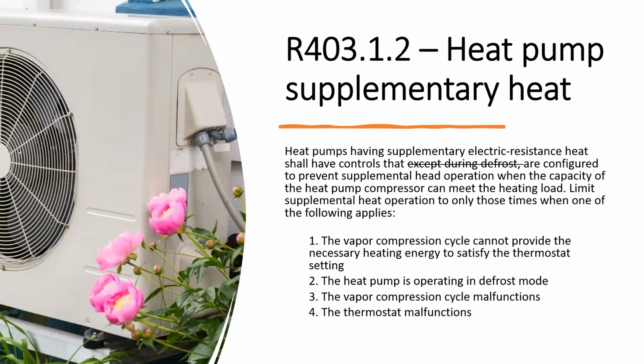Heat pump supplementary heat. I only put this in here where they just scratched out. It used to say heat pumps having supplemental electric resistance heat shall have controls that, except during defrost, they removed that. And it just says are configured to prevent supplemental heat operation when the capacity of the heat pump compressor can meet the load. So they're just trying to say that with the technology that's out there and the things that are happening and the equipment, how they get it put in there, it does still have to go into a defrost cycle.